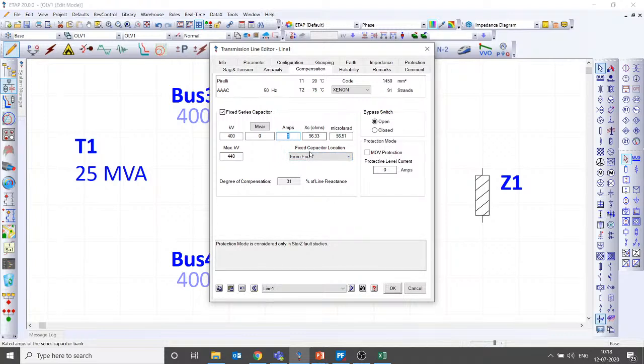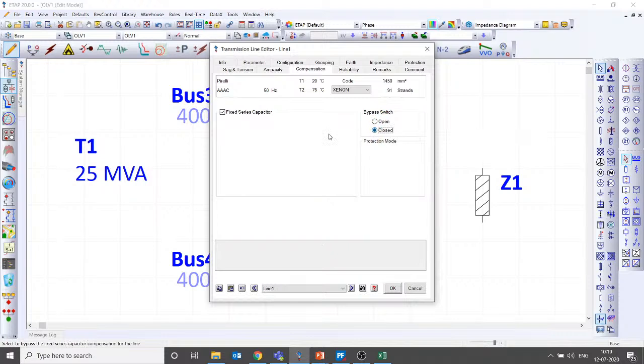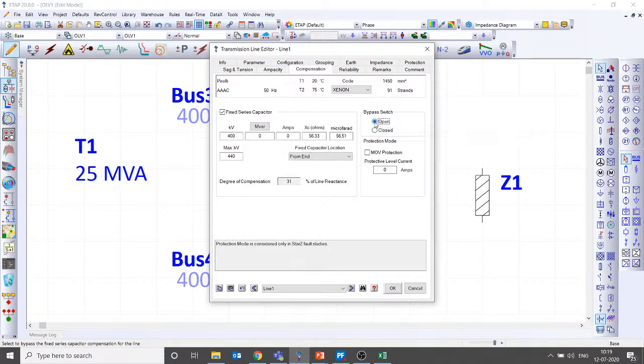Fine. So you can compensate from one end, or you can compensate from two ends. All these things are possible, right? And you can put MOV protections, that's possible, and the bypass which is open or closed. All these things you can take. If the bypass is closed, then the fixed series compensation is bypassed. If the bypass is open, then your series compensation will be in the picture.